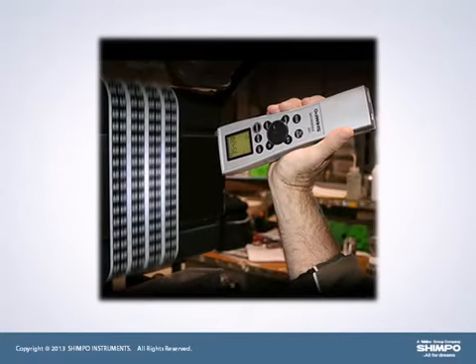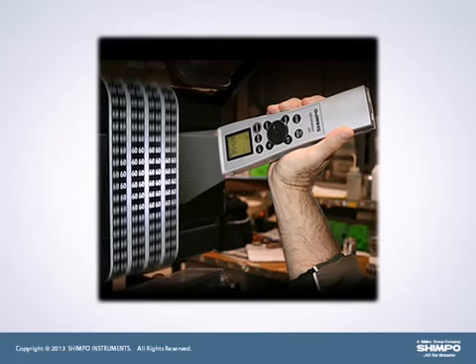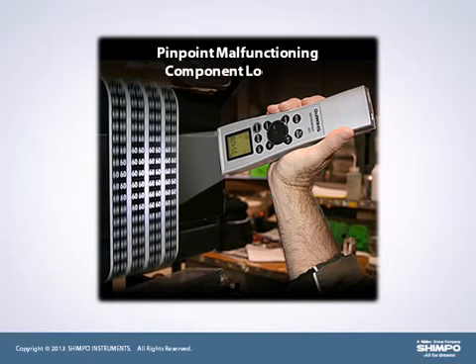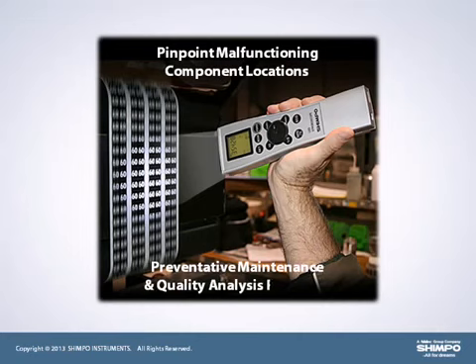When the stroboscope's flash rate is synced with the speed of the equipment, the illusion of slowed or stopped motion is created, allowing further analysis of proper system operation. This phenomenon simplifies pinpointing the location of malfunctioning components, aiding technicians with their preventative maintenance and quality analysis programs.